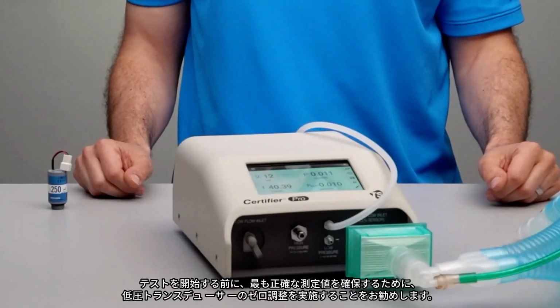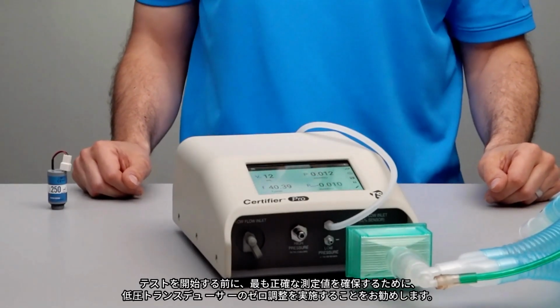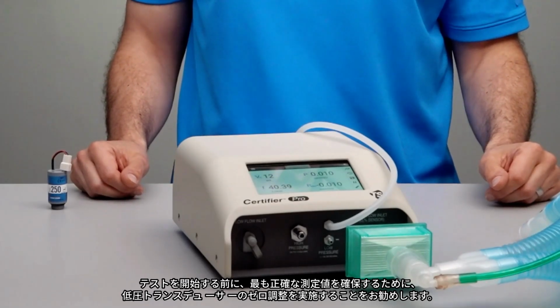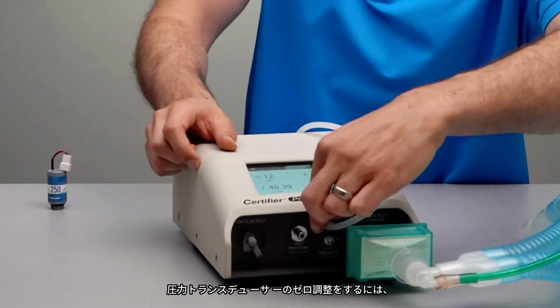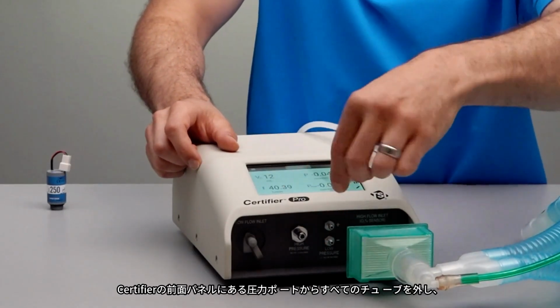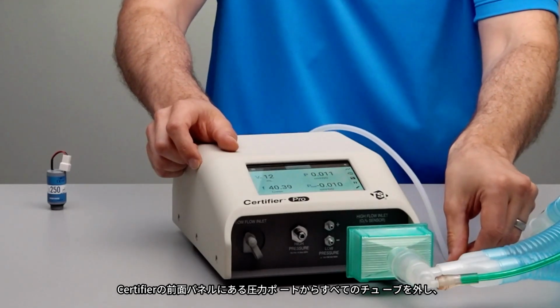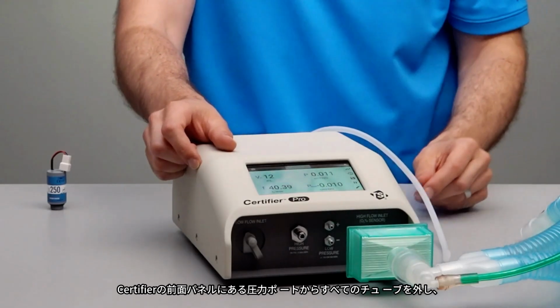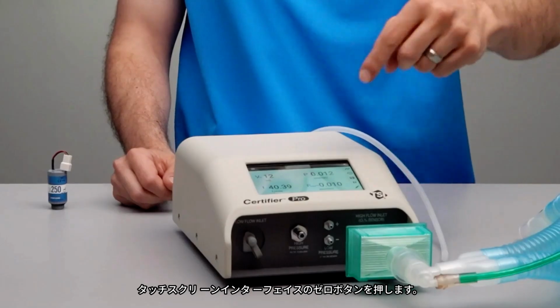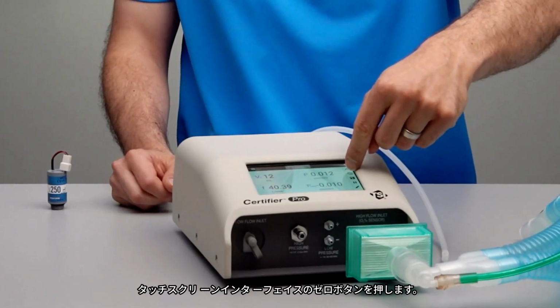Before you start testing, it's recommended to zero the low pressure transducer to ensure the most accurate readings. To zero the pressure transducers, disconnect any tubing from the pressure ports located on the front panel of the certifier, and then press the 0 button on the touchscreen interface.